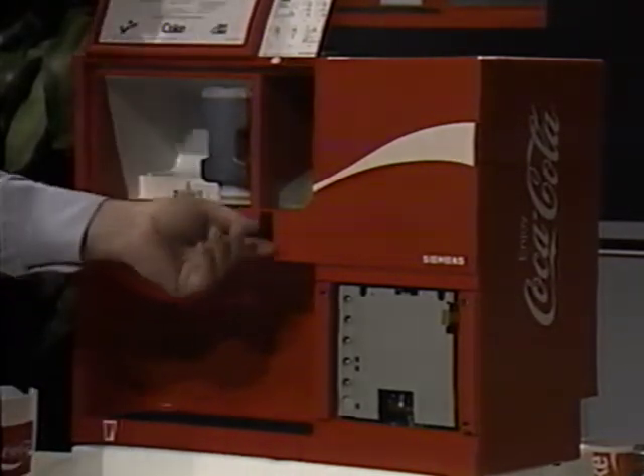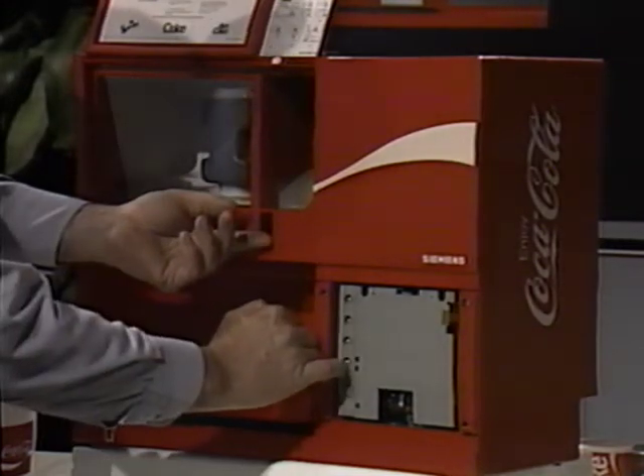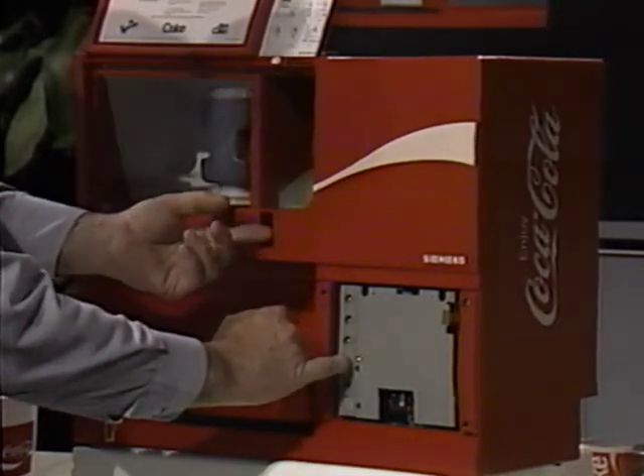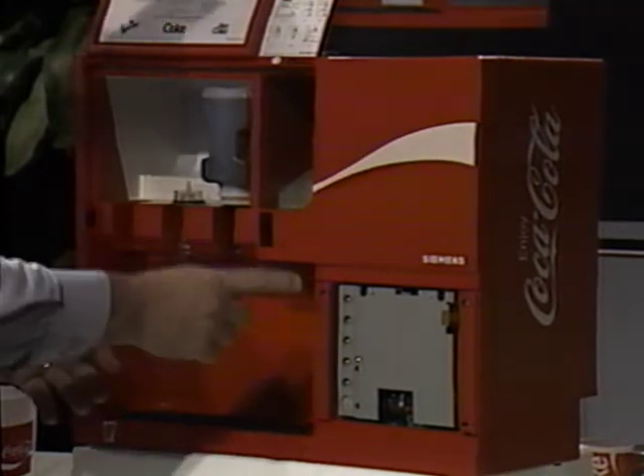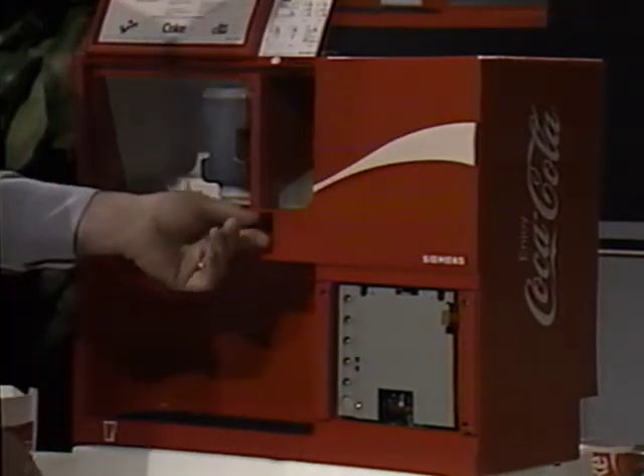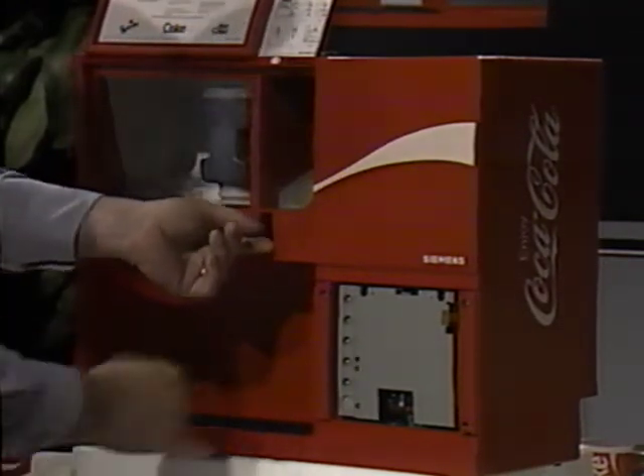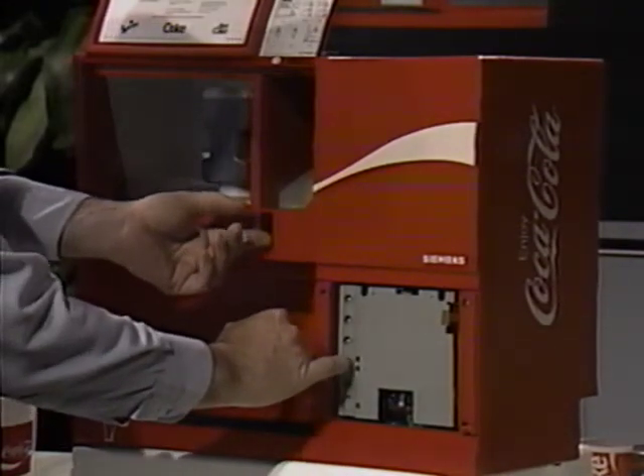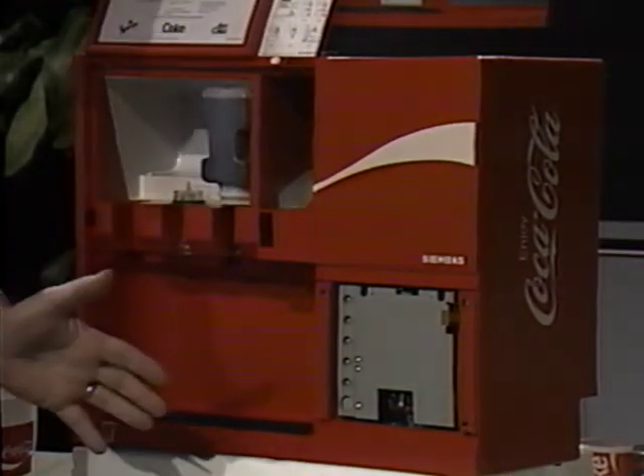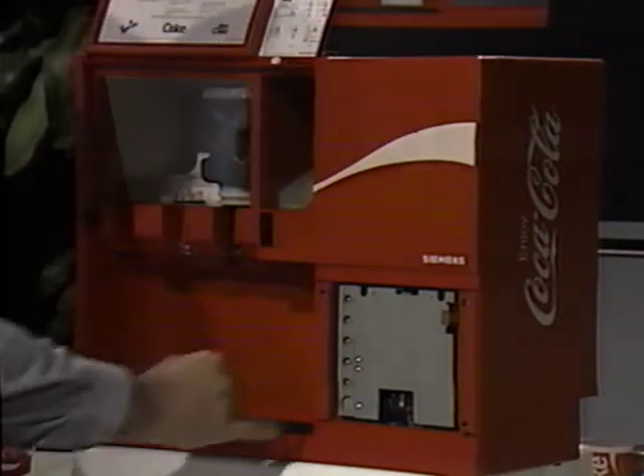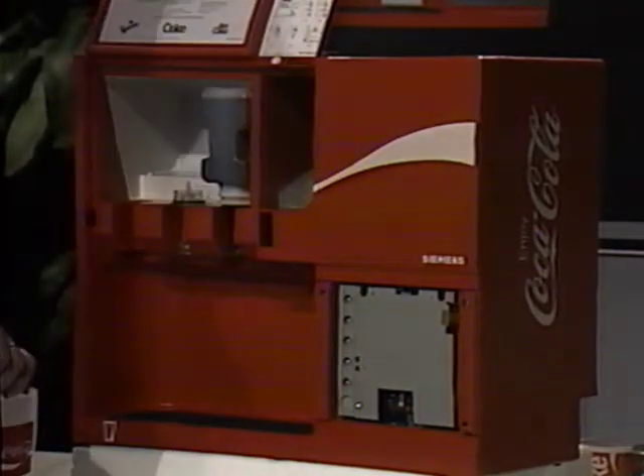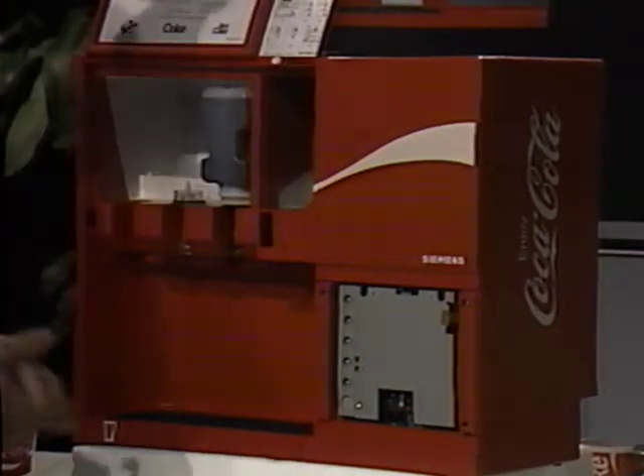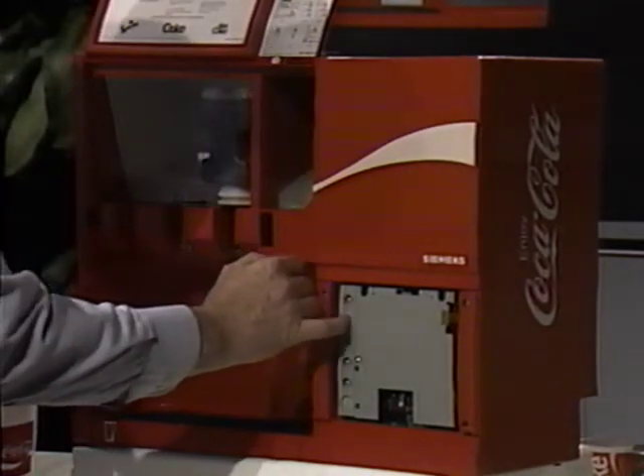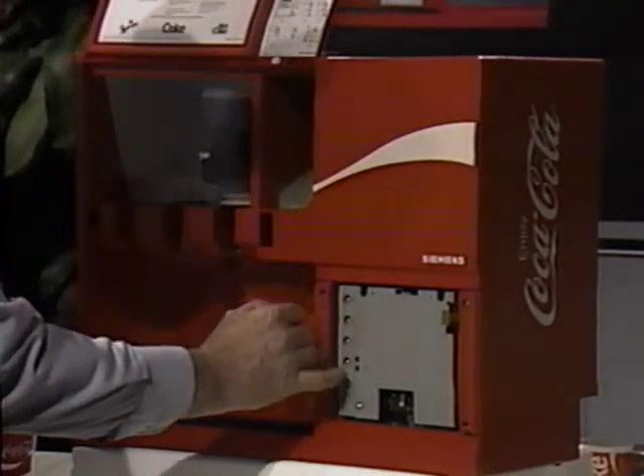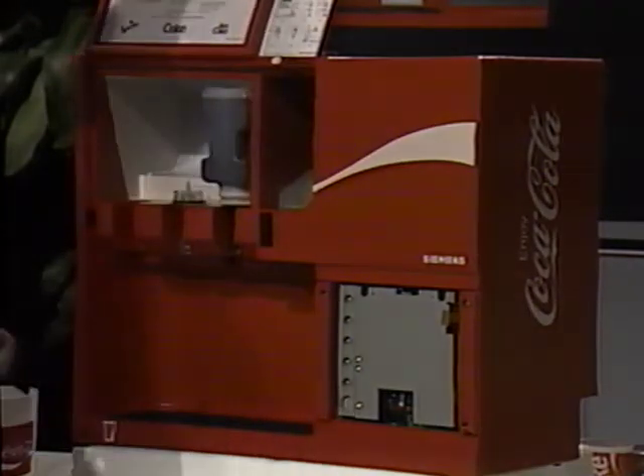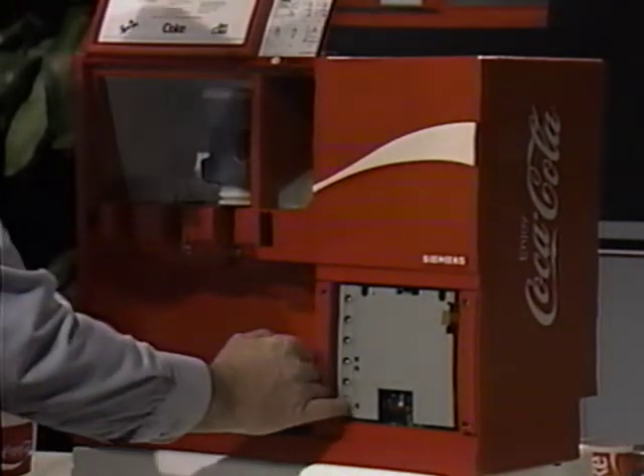And remember how you do that? You press button 4 as you turn on the machine, and you get the blinking lights. Sometimes when putting it in the diagnostic mode, if you turn it on and the buttons are all steady, it only means your super ice is on, and you just punch the button again and then it starts cycling. At this point, check your buttons. Go down through each button. And now you're in the test portion.